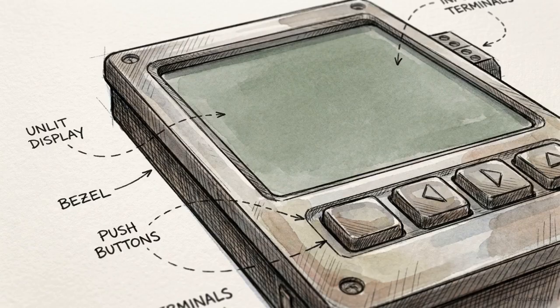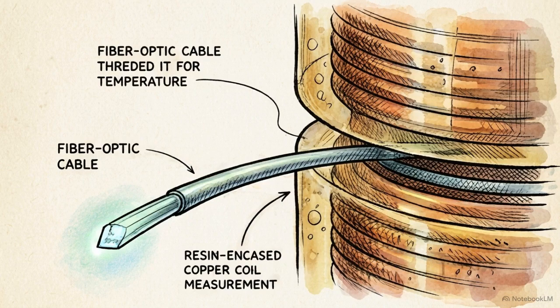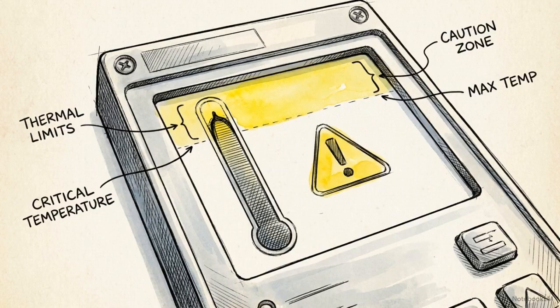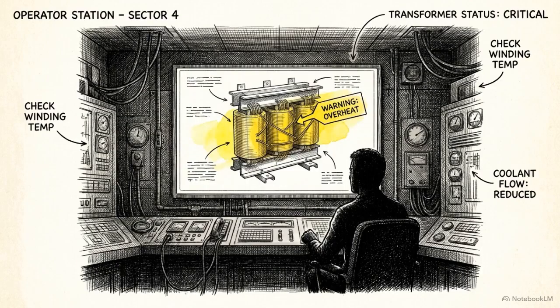To defend against this, we configure the Winding Temperature Indicator, or WTI. We place fiber optic temperature sensors physically inside the dry coils to achieve direct, high-accuracy measurements that are immune to electromagnetic interference. We set our initial WTI alarm limit between 85 and 90 degrees Celsius. This provides an early warning to the control room if the load gets too heavy.